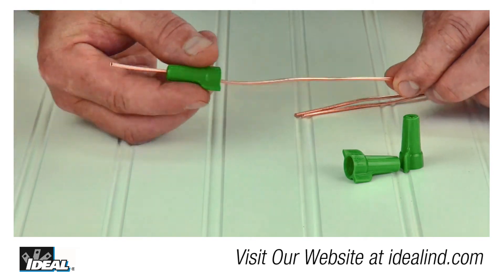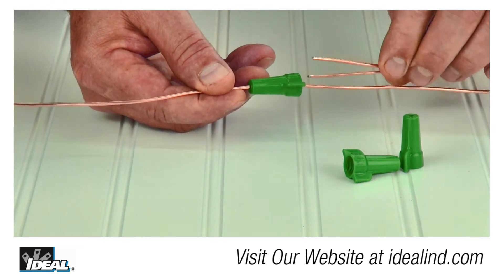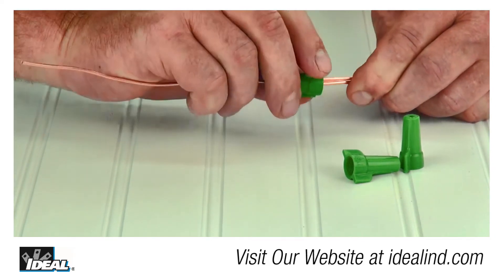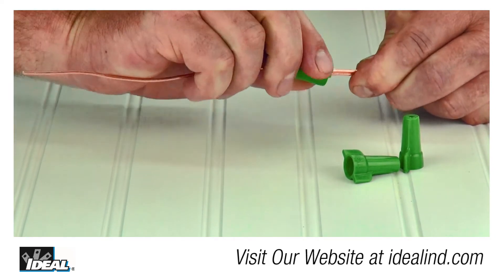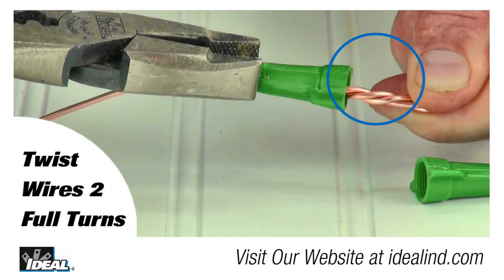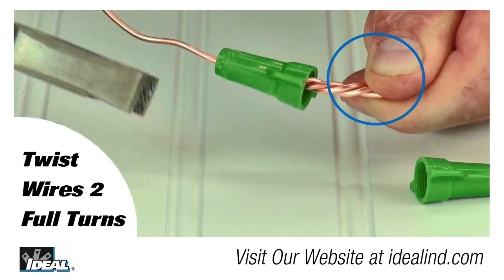Simply pass one of the ground conductors through the hole in the top of the connector approximately six inches past the end of the green wire connector. Then insert the other ground conductors in the connector and twist the conductors multiple times until all the conductors start twisting together outside of the shell approximately two full turns.